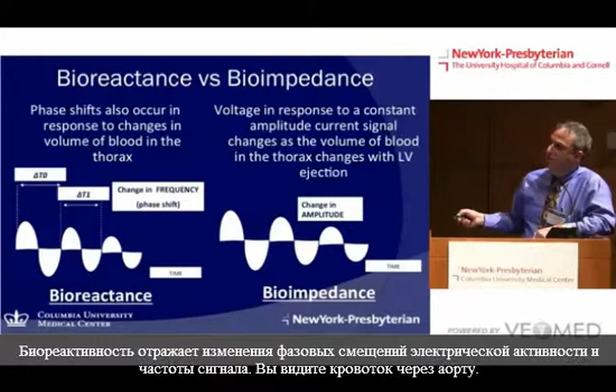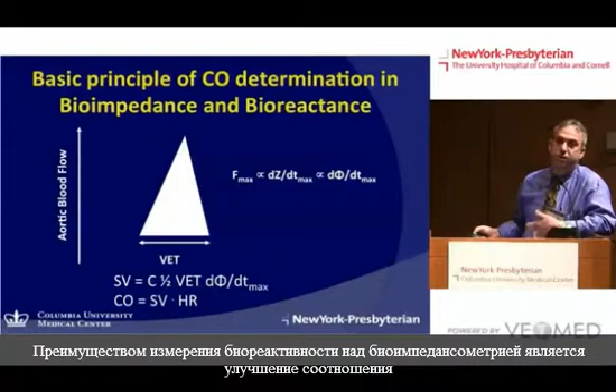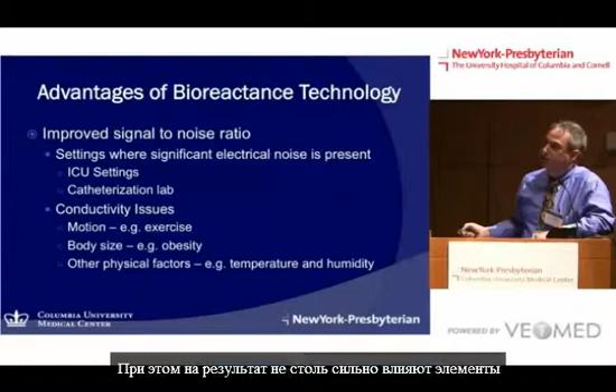Bioreactance relies on changes in the phase shift of the electrical activity and the frequency. And it turns out, if this is, for example, the aortic outflow tract, the stroke volume is directly proportional to this phase shift, by interesting experiments carried out by Dan Burkhoff and others. So you can non-invasively estimate one's stroke volume on a beat-to-beat basis using this technology. The advantage of bioreactance over bioimpedance is improved signal-to-noise ratio, so in settings where there's a lot of electrical and mechanical interference, it may be better. And again, there are conductivity issues where body size, motion, and other physical factors don't impede as much.